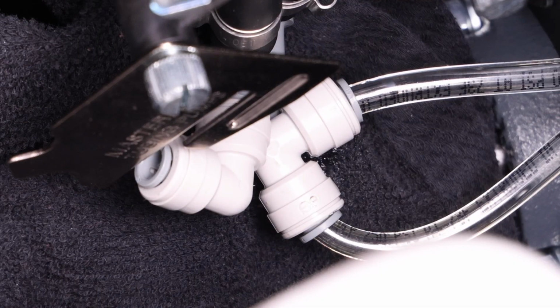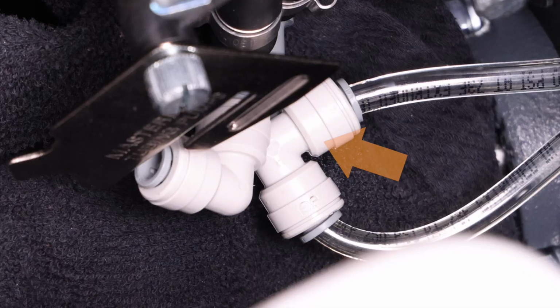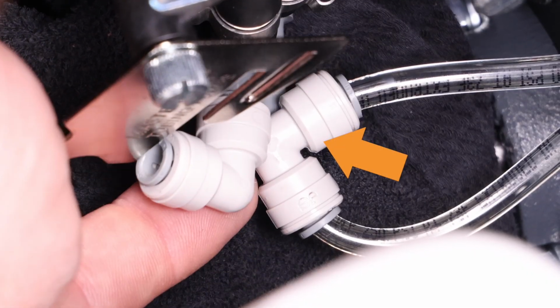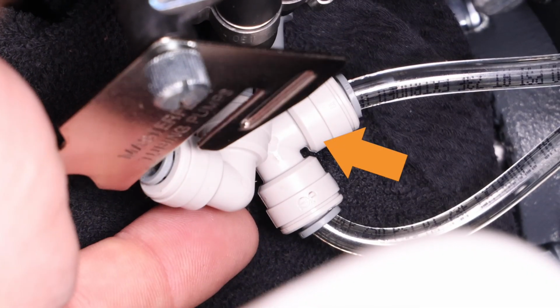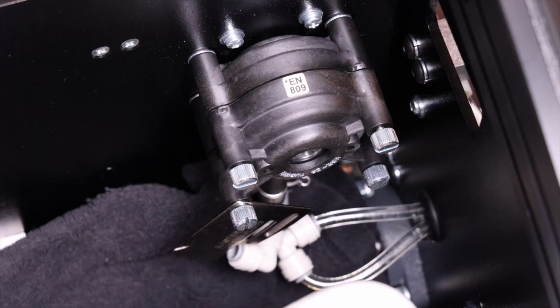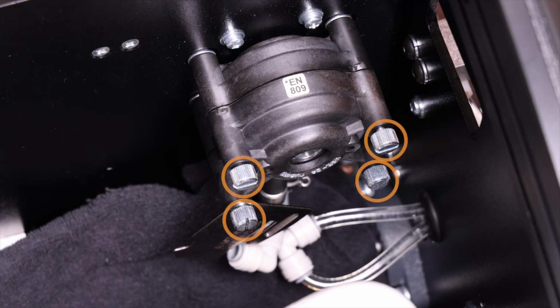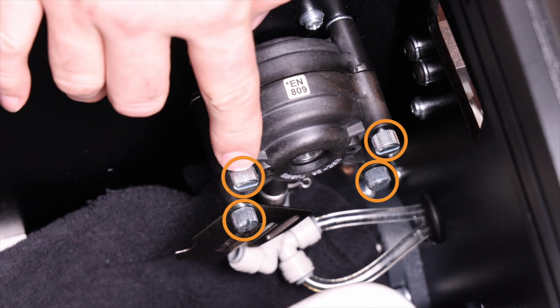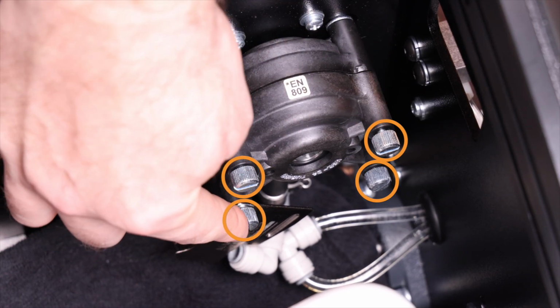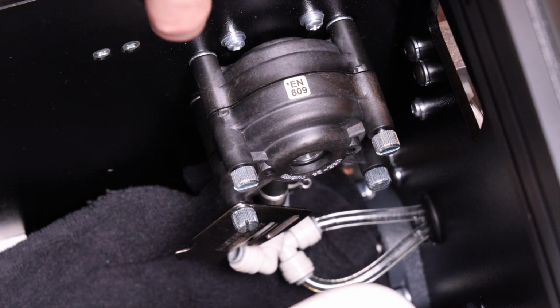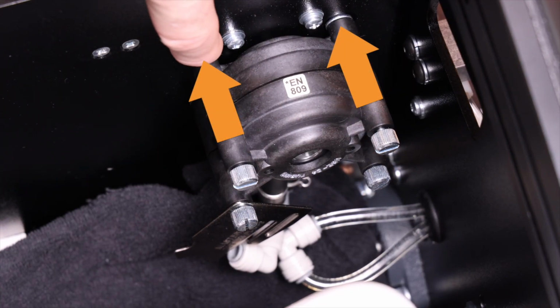Another helpful tip after labeling which line is which is to use one of the fittings off the pump to plug the lines. I've also taken the liberty of loosening our hardware on our pump assembly. Remove the 4 knurled screws, being cautious of the washers on the back side between the pump and the motor assembly.